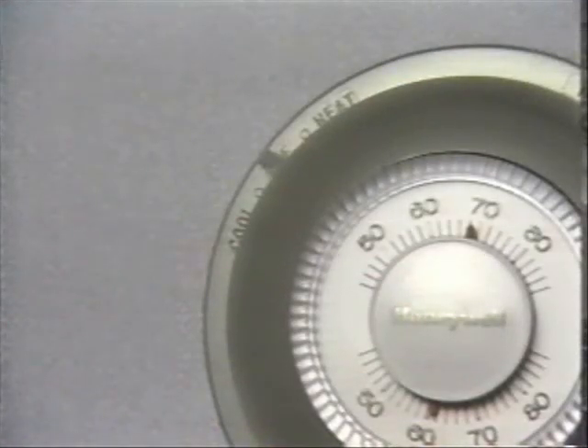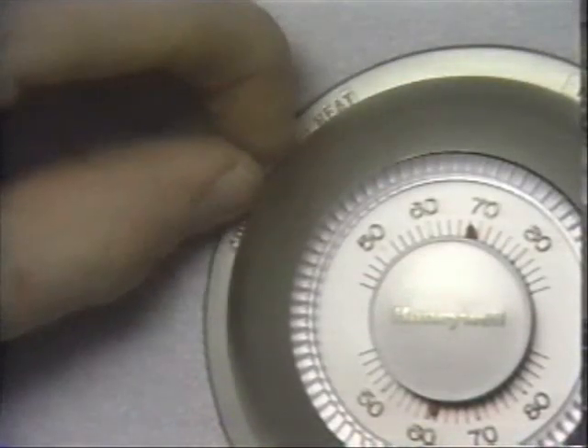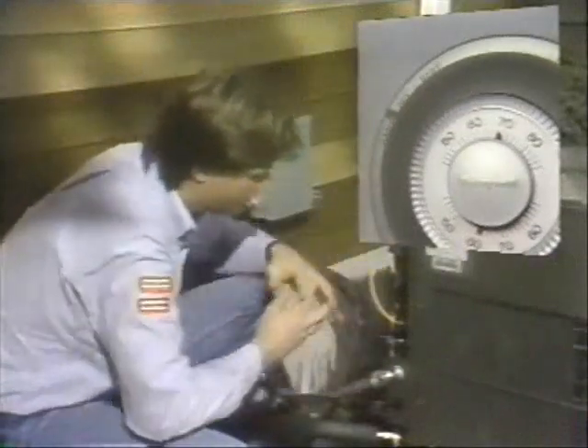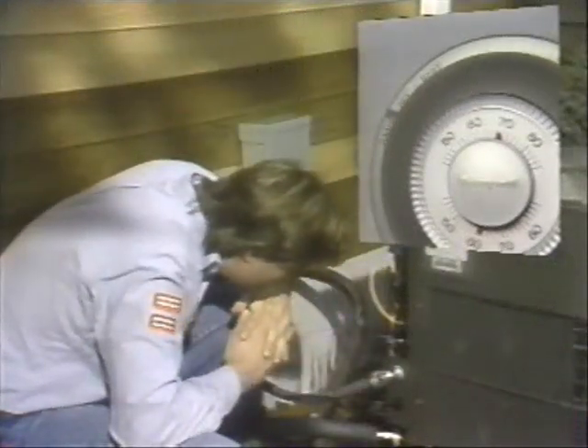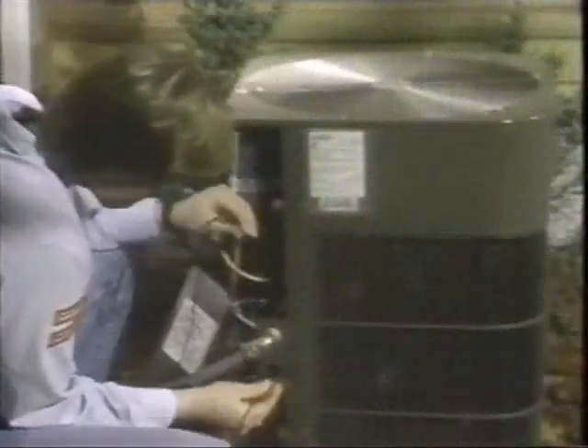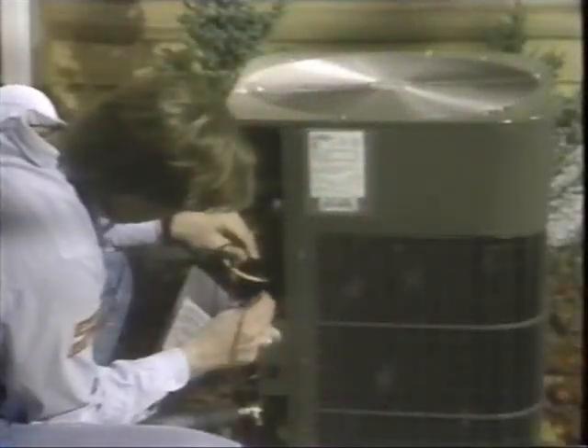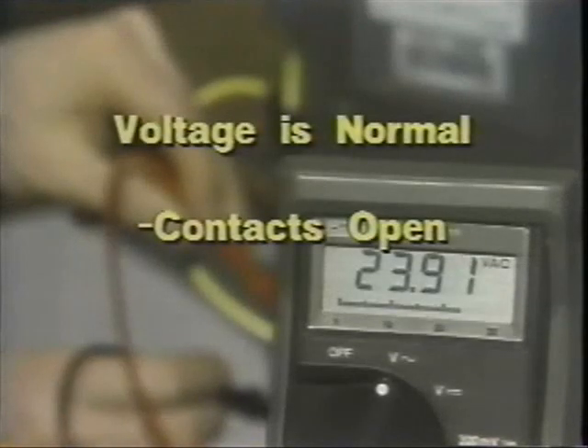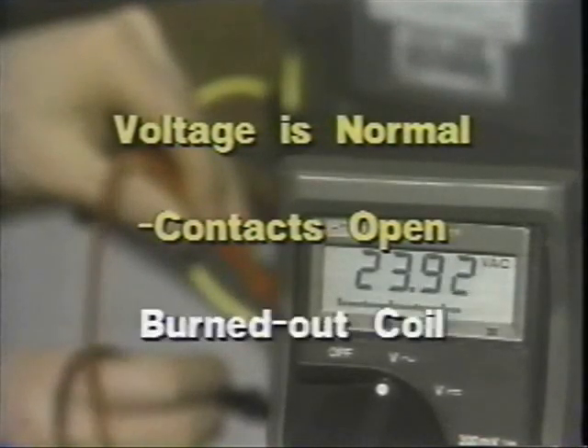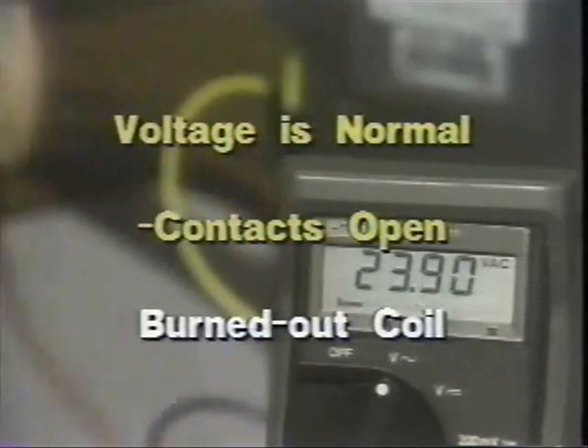In a system that doesn't even start, set the thermostat for cooling. Observe the contactor to see whether the contacts close. If contacts do not close, check the voltage at the coil terminals. If the voltage is normal and the contacts are open, you've probably got a burned out coil. If the contactor does pull in, your next step is to see if you're getting voltage through the contacts. Arcing burns away the contact surfaces and prevents conduction of current through the contacts.